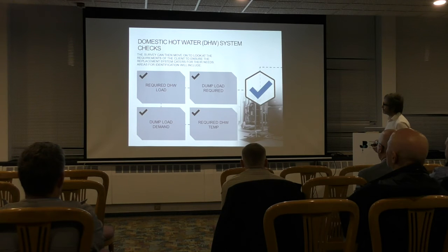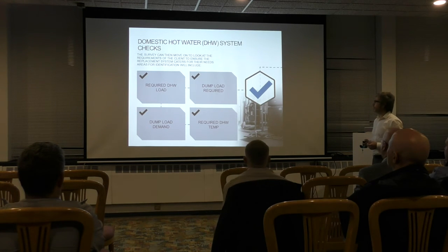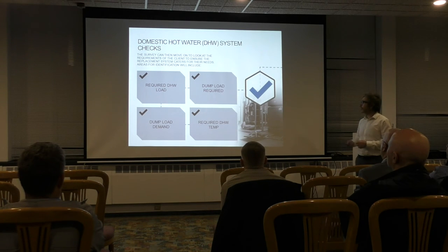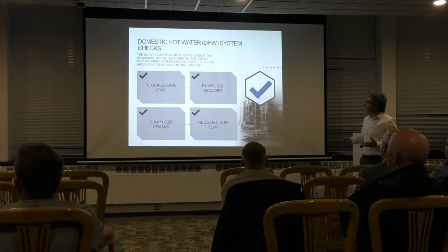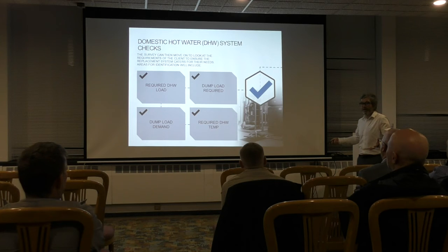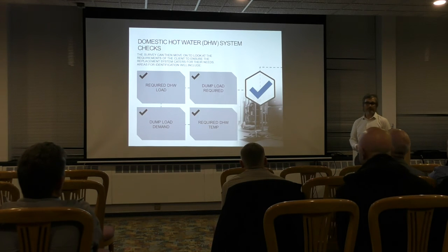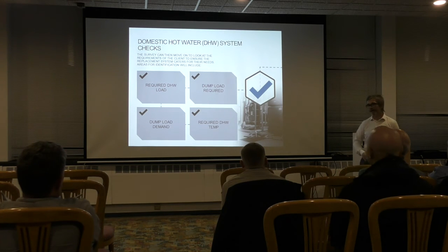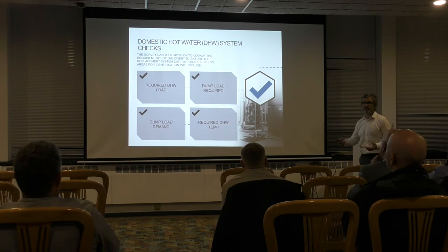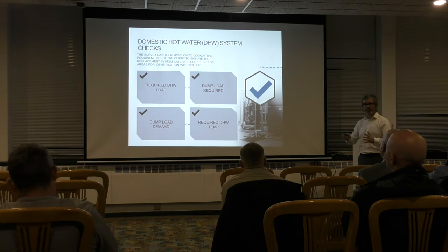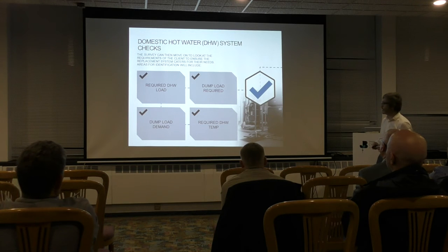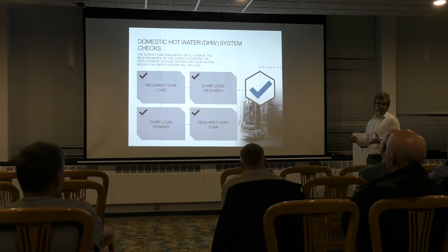And then moving on from there, when we are looking at domestic hot water, things like system checks. So, looking at the domestic hot water load, is it adequate? Do we need to start looking at putting a dump load in? When we talk about dump loads, we're talking about at peak time. So take, for example, a hotel. If it's a business hotel and you've got people getting up between 6 in the morning and 7:30, you've got an hour and a half period where you're going to have a lot of people showering. So it could be that we might need to start looking at putting in more stored water, essentially.